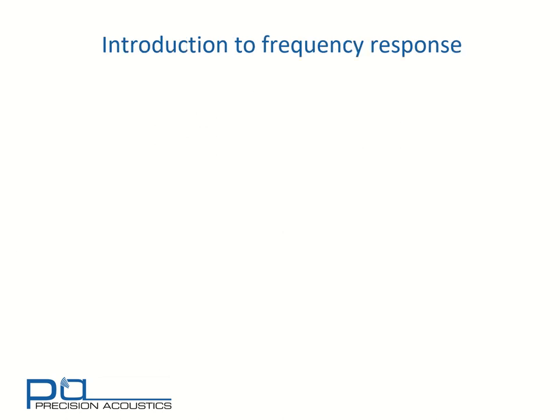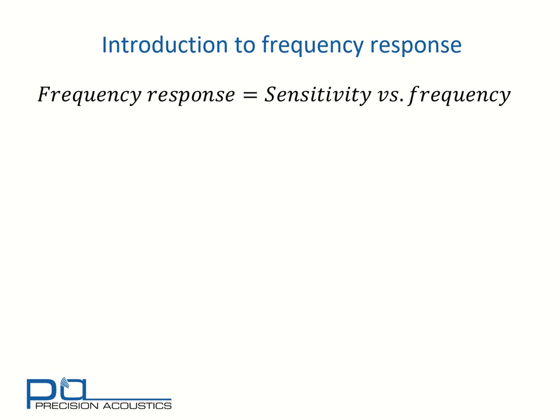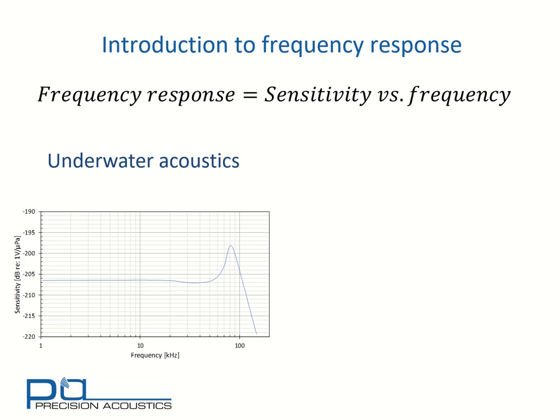We'll now go on to consider frequency response, which is the variation of sensitivity as a function of frequency. In underwater acoustics, where hydrophones are typically small relative to the wavelength being measured, we find that frequency response can be largely constant, certainly in regions where we are below thickness or radial resonances. In the case of the hydrophone shown on the left hand side, below 30 kHz we have a pretty constant sensitivity.